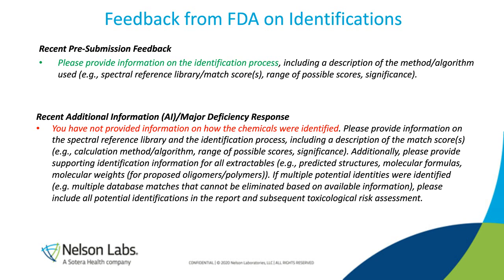And this reminds me to touch on the power of the pre-sub, right? So we see the same feedback, oftentimes word for word, in both pre-sub commentary and in major deficiencies. And so I think it makes a lot of sense that it's better to have this feedback up front, either ahead of starting testing, or even while testing is in play. If you initiate testing while you're waiting for a pre-sub, it's better to have this feedback sooner rather than later. And the pre-sub process is a great way to do that, and it is something that we help with routinely. We support pre-subs, and we'll talk to the FDA for you and all these sorts of things. And this is something that I would highly recommend.